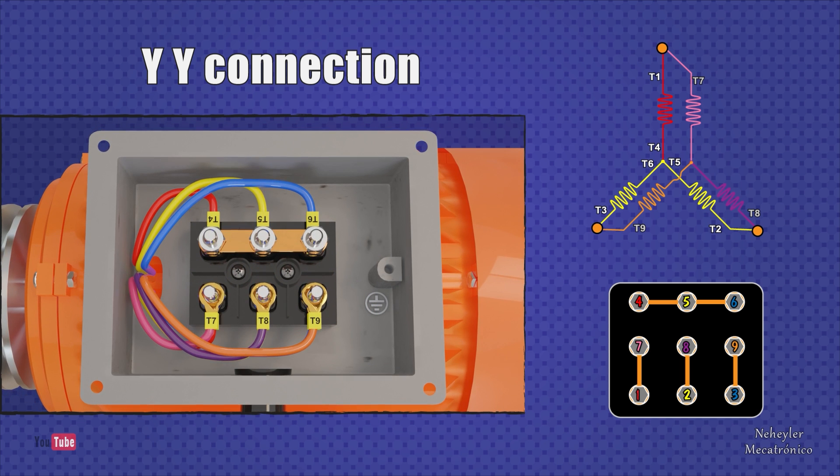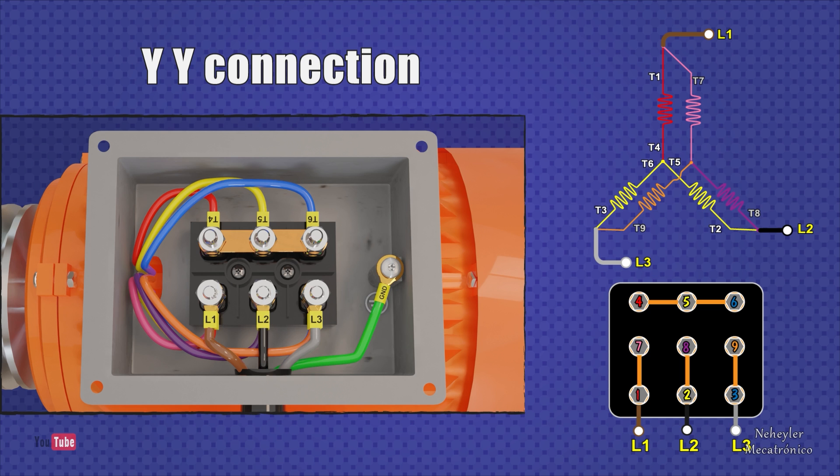Terminal 7 should be joined to Terminal 1, Terminal 8 to 2, and Terminal 9 to 3. Finally, we connect the power cables. L1 next to T1 and T7, L2 next to T2 and T8, L3 next to T3 and T9. Keep in mind that the ground protection cable must be added.